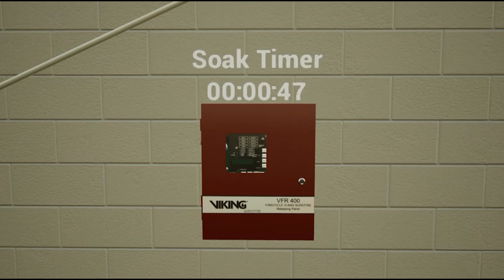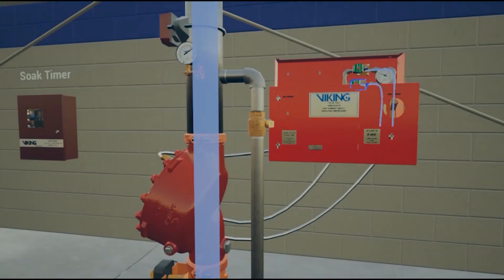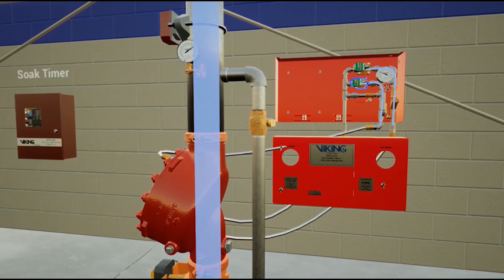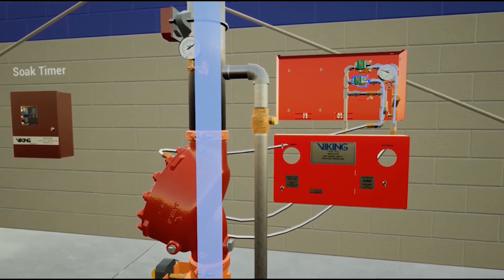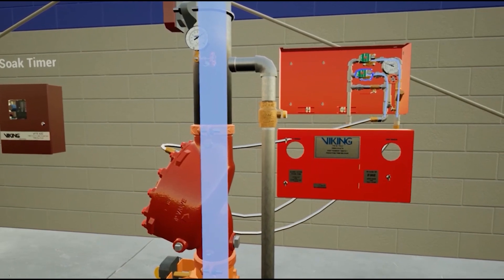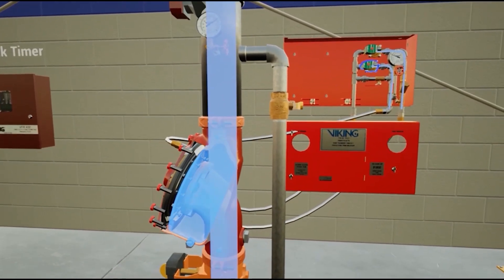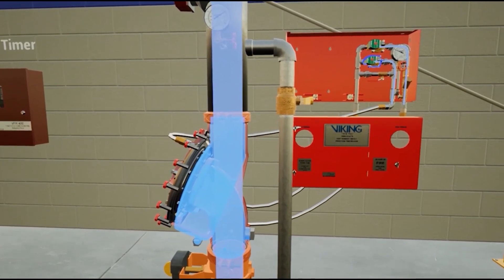Upon the expiration of the soak timer, the power is removed from the normally closed solenoid valve, allowing it to close. With the normally closed solenoid valve returned to its normal state, the water pressure will begin to re-establish in the priming chamber.